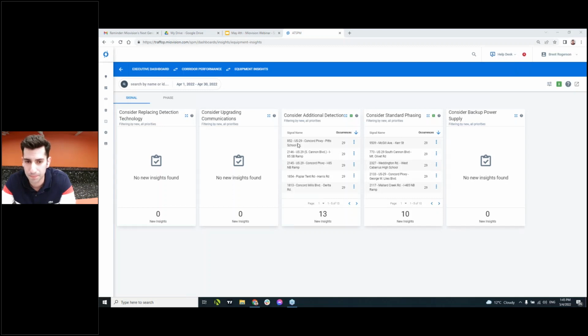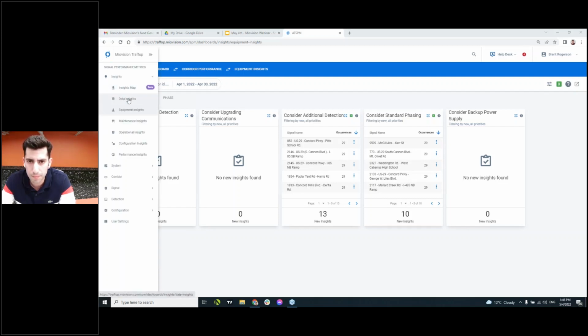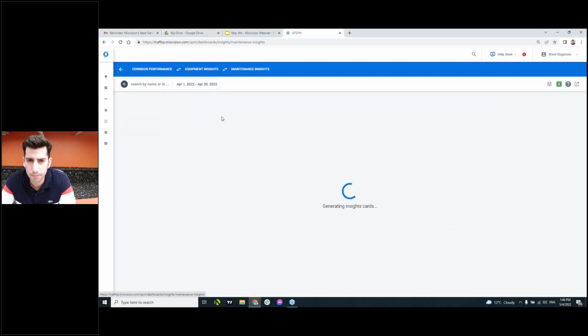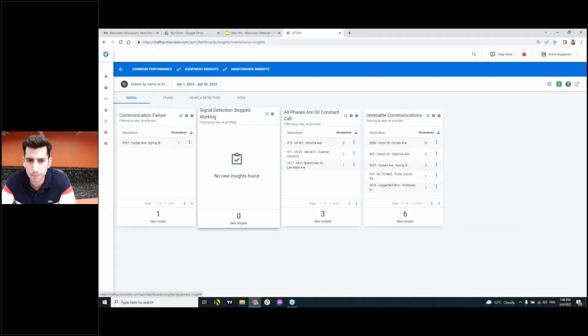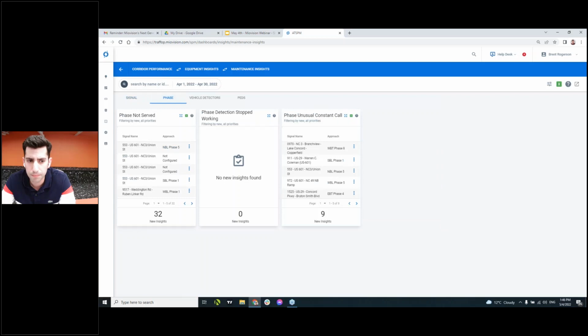Yeah, for sure. Sorry, I should have probably included that slide in the presentation. I should have anticipated that question. So there's a series of different types of severity. Critical issues like power loss or flash alerts would be your highest level. Those would certainly be the most impactful in terms of equipment insights and maintenance insights. So I'll go back here for a second. Really understanding, is it safely operating? And if it's not safely operating, like signal flash states, those are your highest priority. Those are the critical alerts.